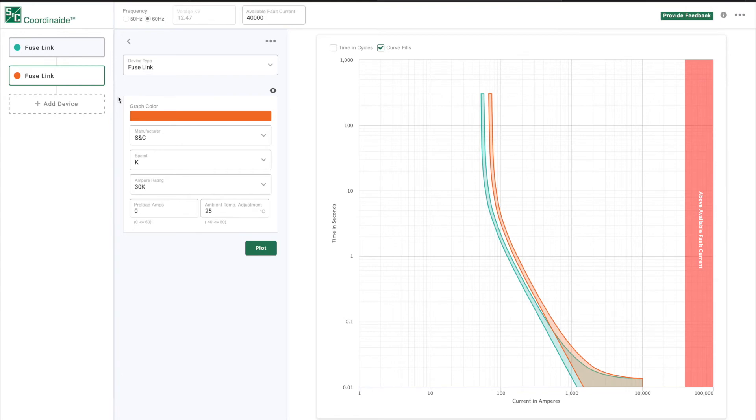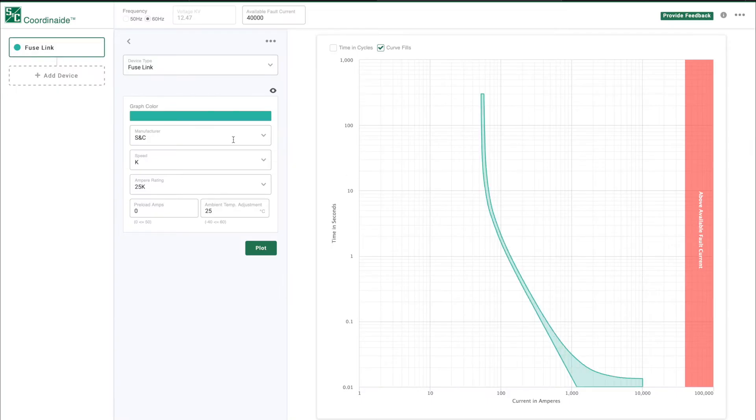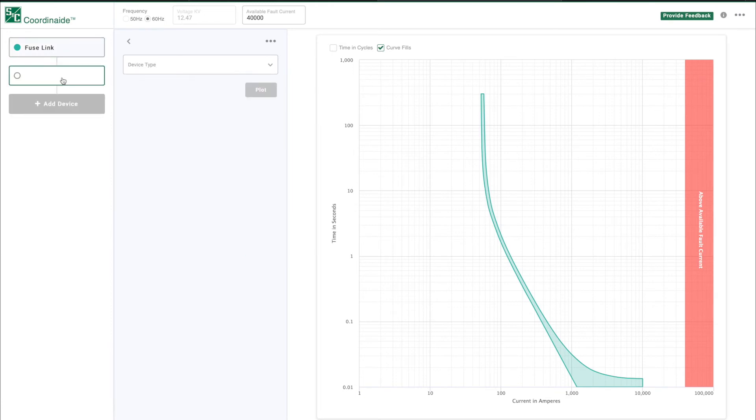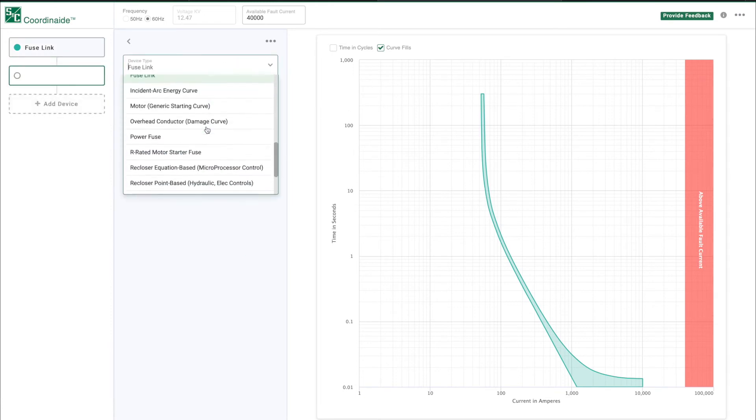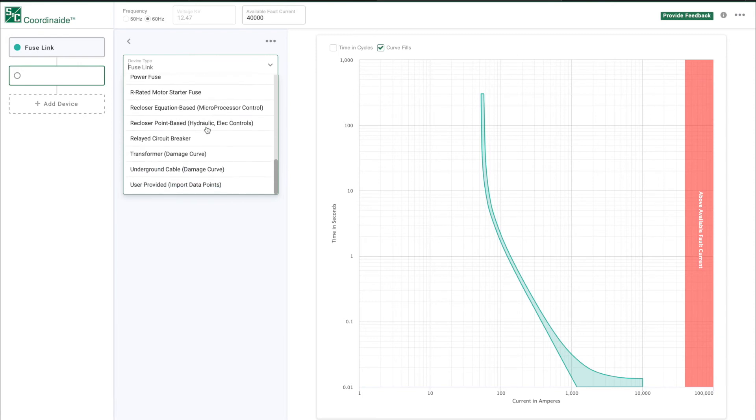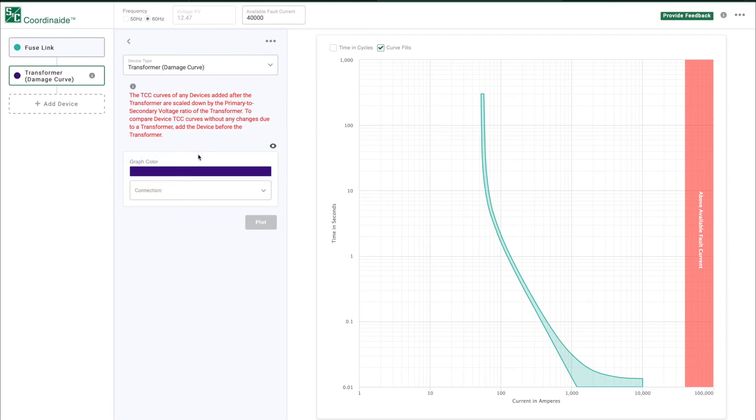Delete the second fuse by making sure it's selected, click on the three dots and choose Delete Current Device. Now click on Add Device under the fuse link. In the Device Type field, select Transformer Damage Curve. This plots industry standard damage curves for transformers.